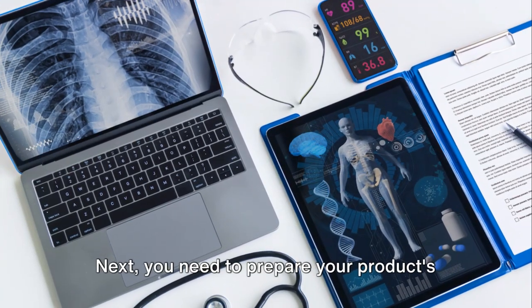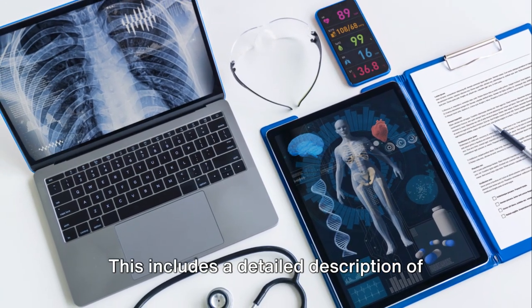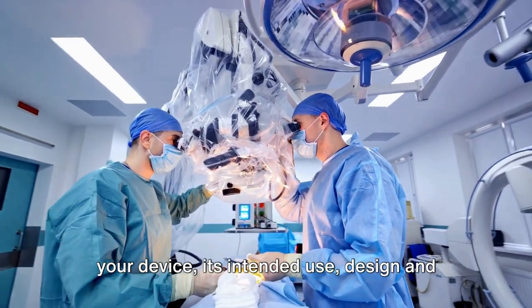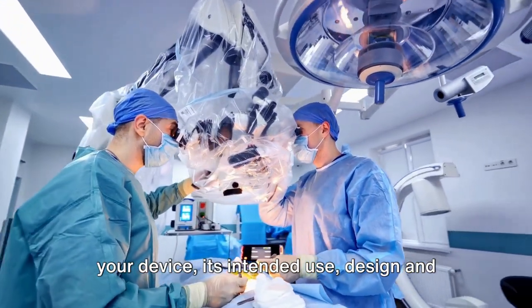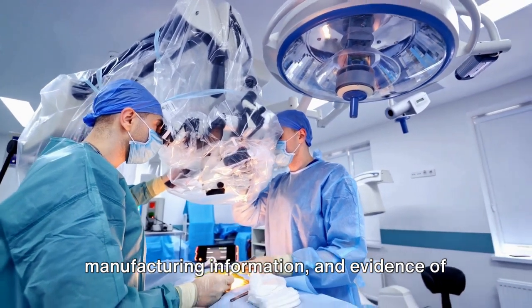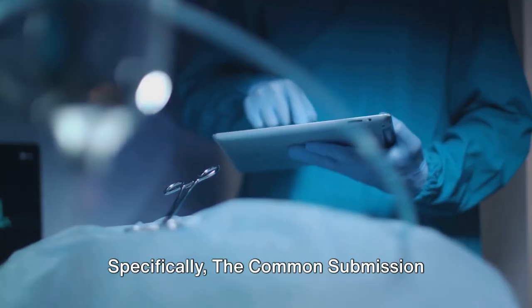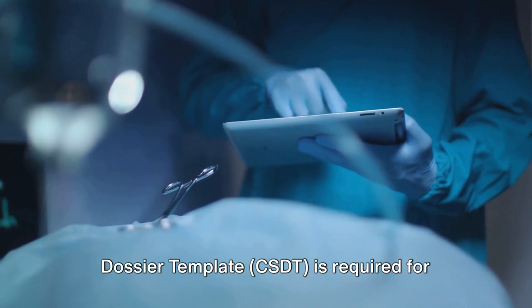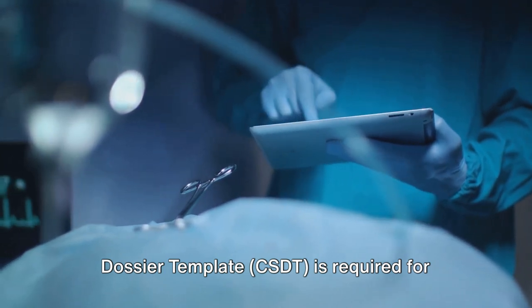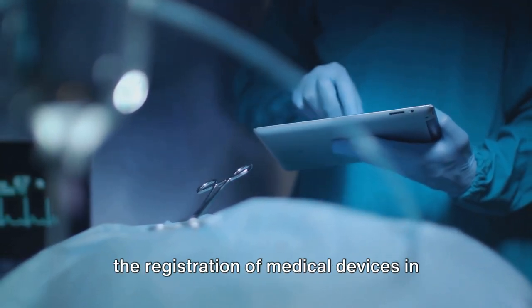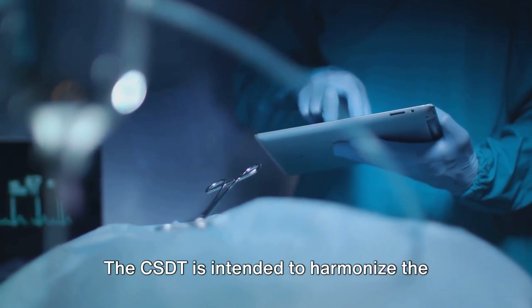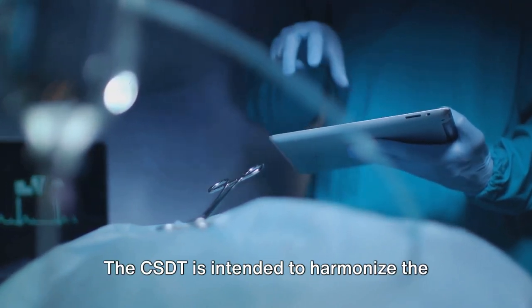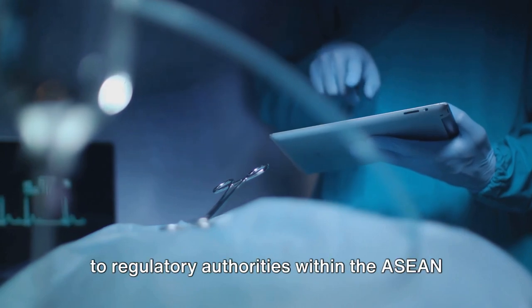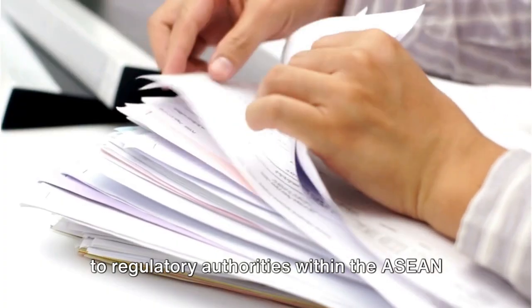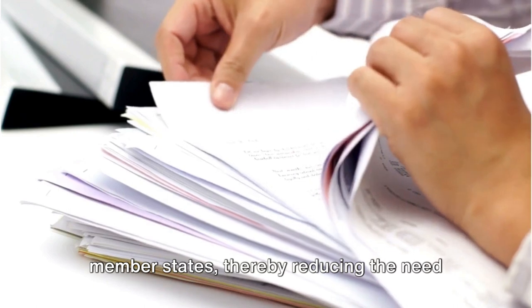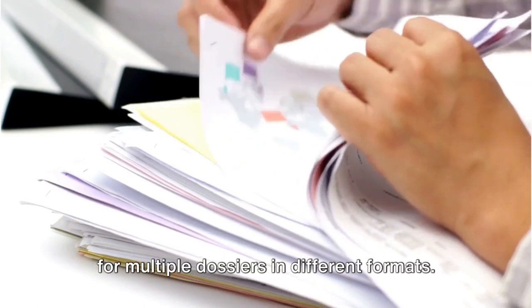Next, you need to prepare your product's technical documentation. This includes a detailed description of your device, its intended use, design and manufacturing information, and evidence of safety and effectiveness. Specifically, the Common Submission Dossier Template, CSDT, is required for the registration of medical devices in ASEAN countries. The CSDT is intended to harmonize the submission of medical device information to regulatory authorities within the ASEAN member states, thereby reducing the need for multiple dossiers in different formats.